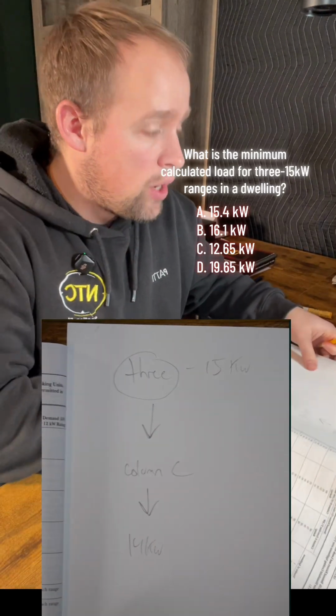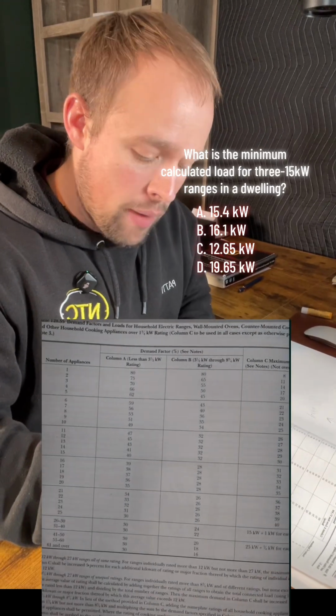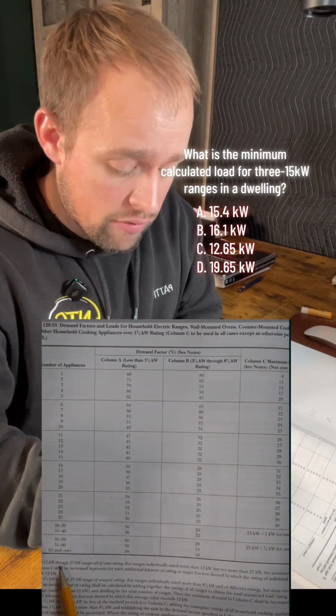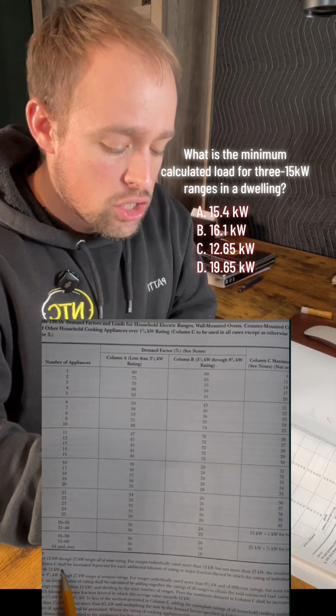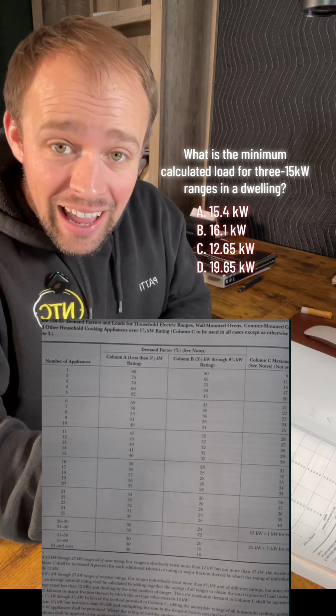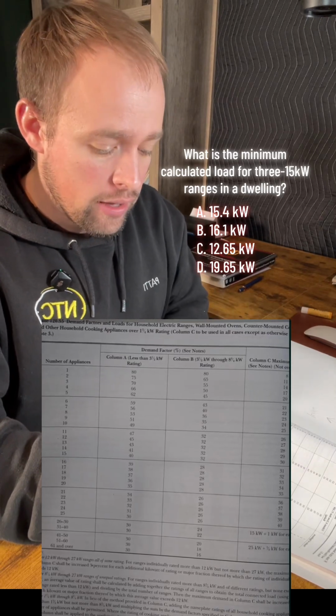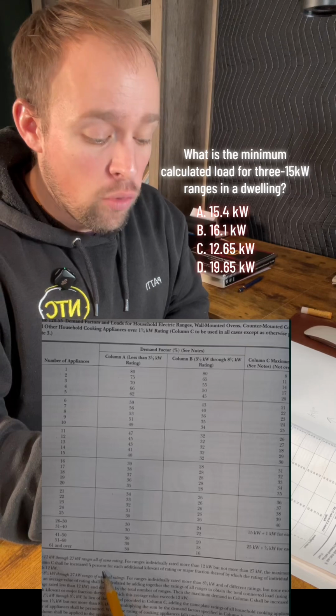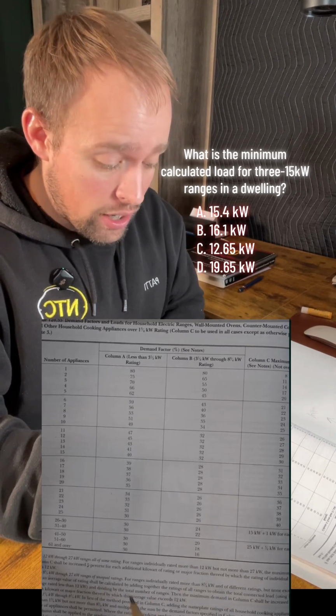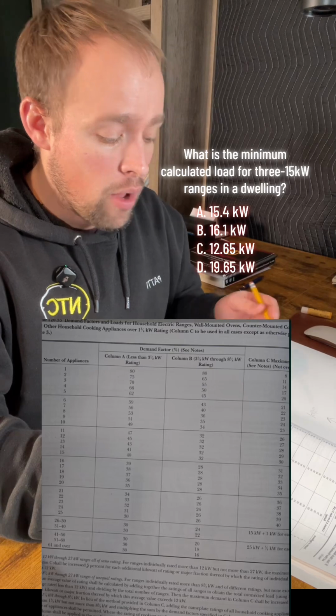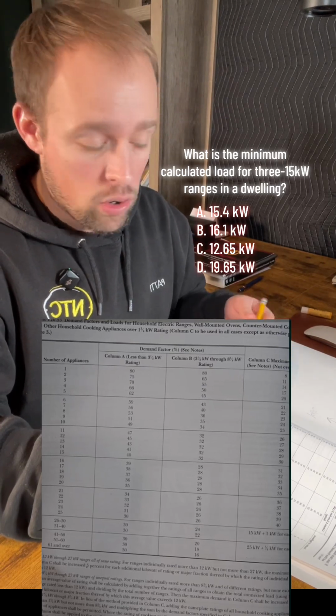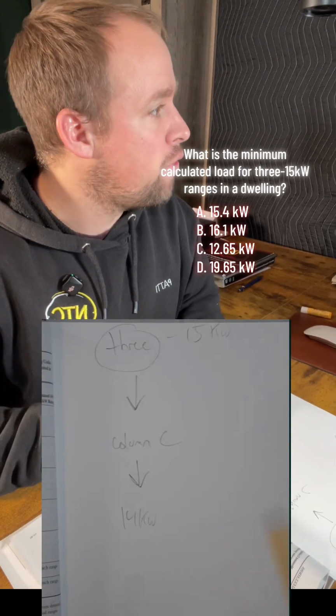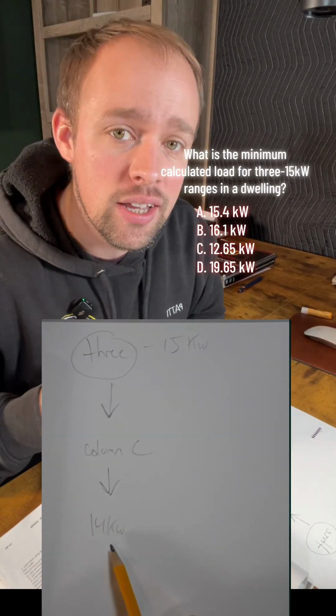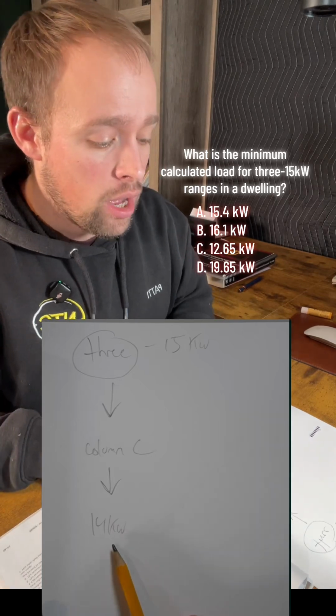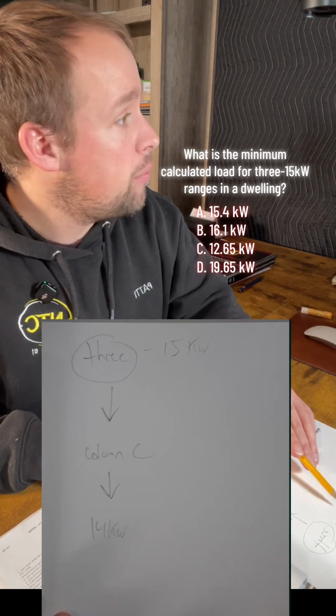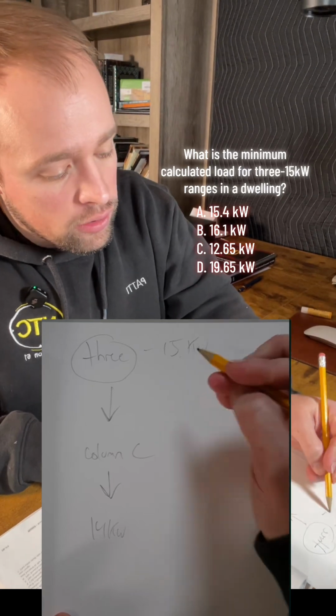So now let's continue reading that note. The maximum demand in column C, which we just got, 14 kW, shall be increased by 5% for each additional kilowatt of rating or major fraction thereof, by which the rating of individual ranges exceeds 12 kW. Okay, so this 14 kW has to be increased by 5% for each kW over 12.